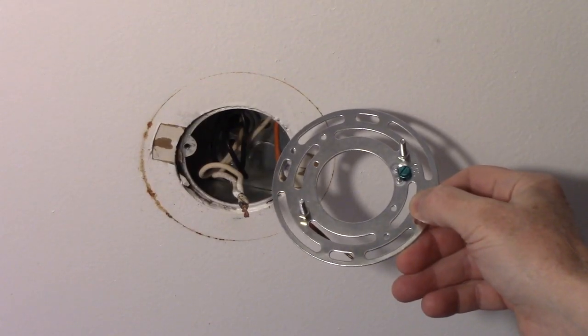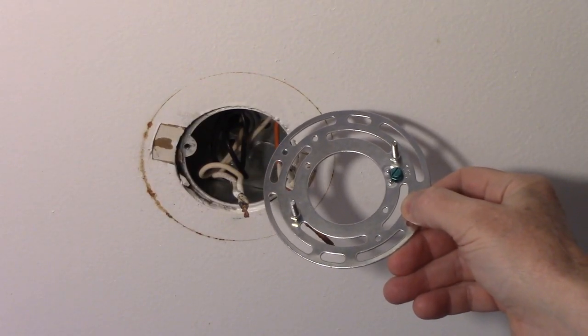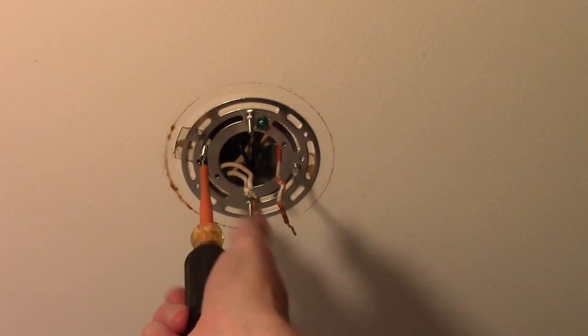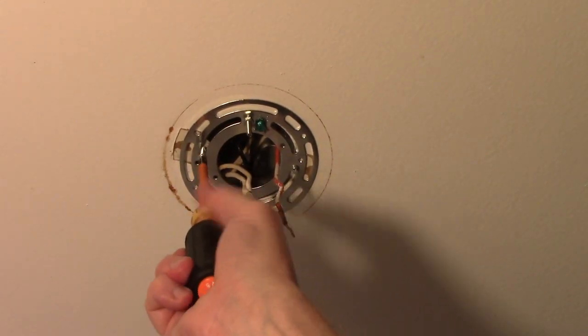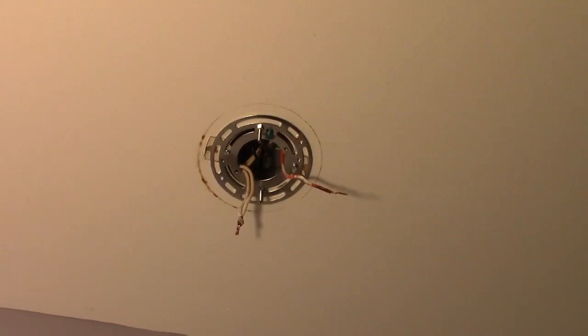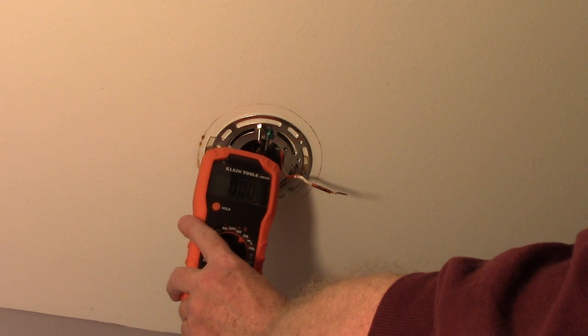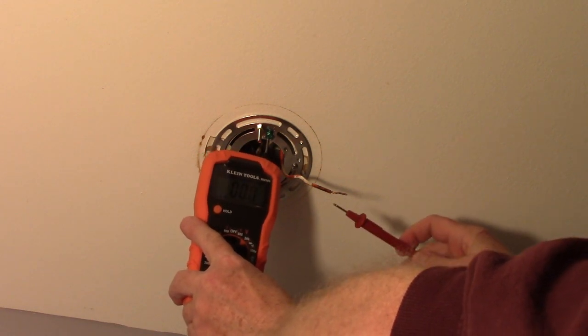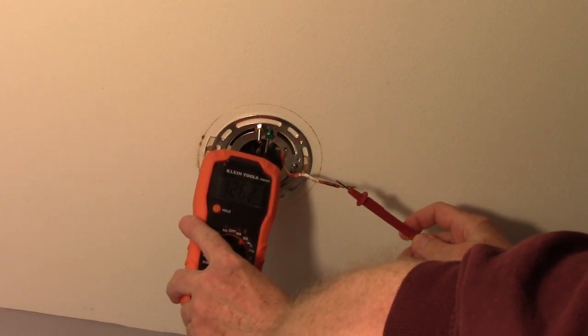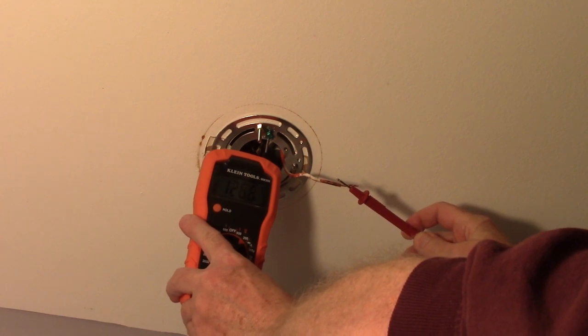I'm going to connect the mounting plate that came with the light to the box with two screws. Now that I have the mounting plate screwed to the box, I can confirm that that plate is grounded. I'm going to touch the grounding screw on the plate with one probe. I turn my electric back on and I touch my power, and you can see it's showing 120 volts.